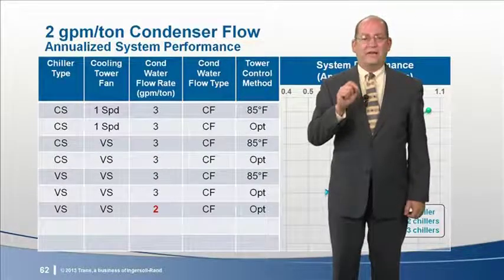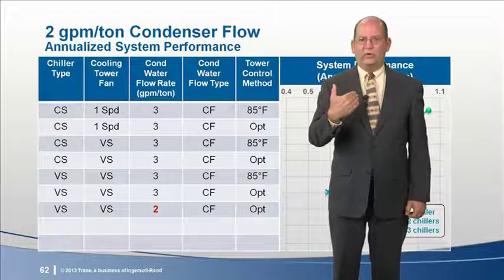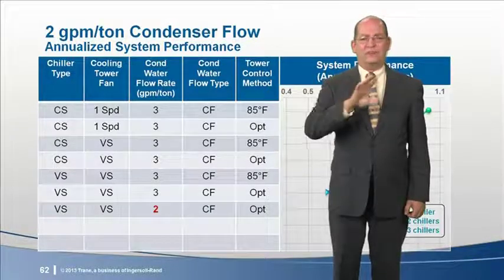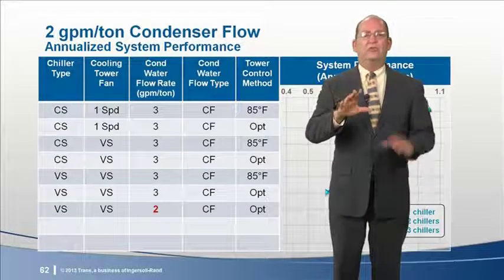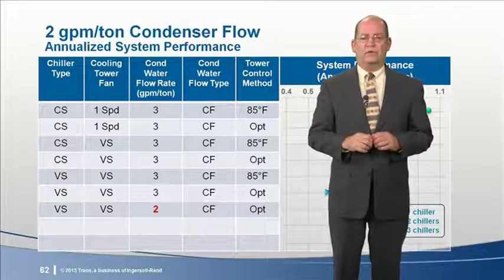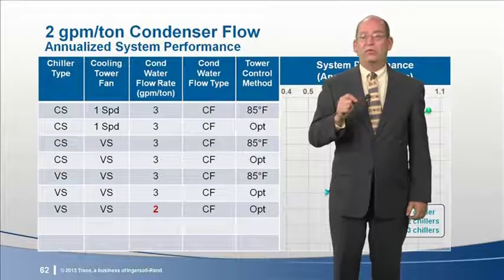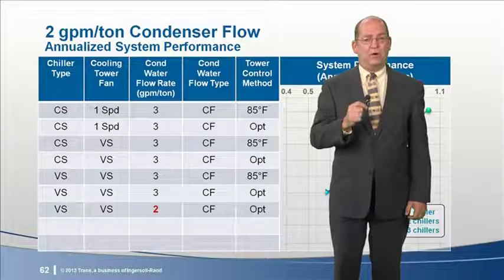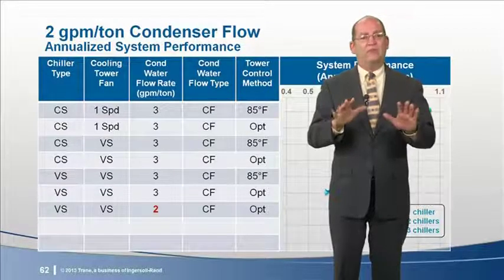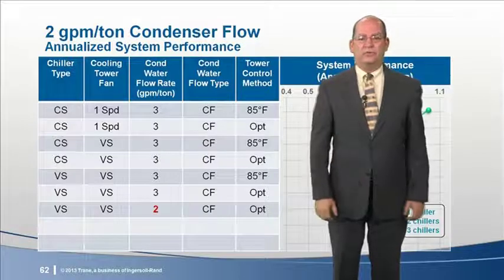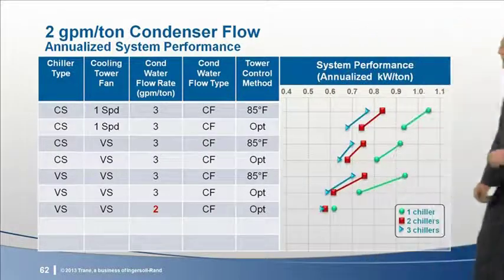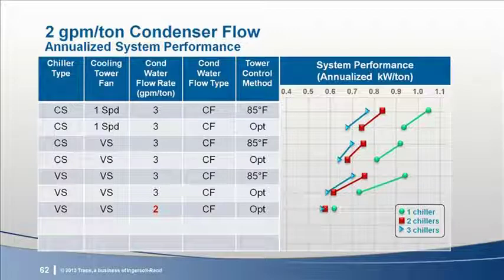Since we're looking at strictly energy consumption, when we reduced the condenser water flow rate, we left the pipe sizes the same, and used the same cooling tower fan. Reducing tower flow rate results in reduced condenser water pump power and energy, as well as a closer cooling tower approach temperature. The result shows lower design flow rate provides very good savings for fewer chillers. But as the number of chillers increases, performance differences are less significant.